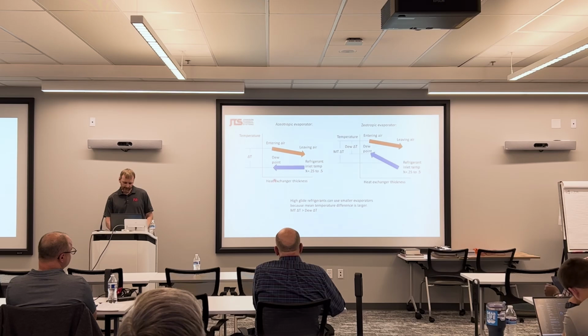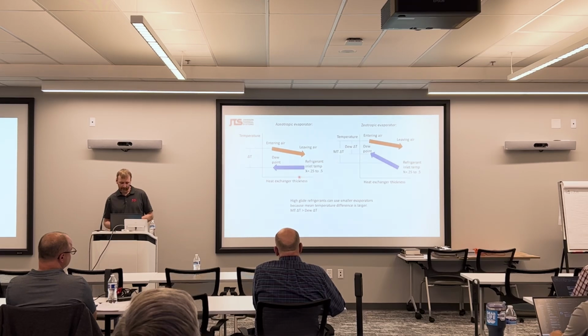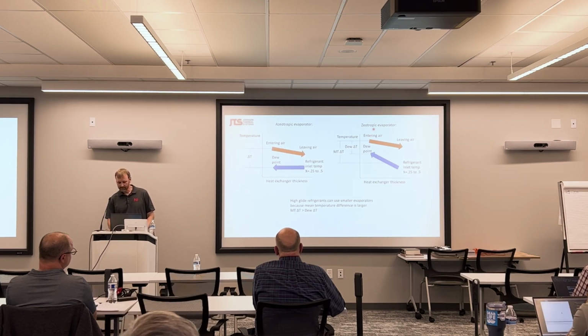So to illustrate the same basic function that's happening inside of the evaporator, again, we're going to plot the temperature versus the heat exchanger thickness. Evaporators are similar to condensers in the sense that they usually have counterflow heat transfer. With a traditional azeotropic refrigerant, your refrigerant inlet temperature to your dew point stays about the same temperature. You don't have a change in temperature as that refrigerant boils. However, you're cooling the air from a warmer temperature to a lower temperature. With a zeotropic refrigerant, you still need the dew point delta T. This is necessary for any evaporator in order to generate superheat. However, because your refrigerant has glide, your mean temperature delta T is larger. Therefore, one thing that's common is your evaporators typically gain efficiency when you're using high glide refrigerants.